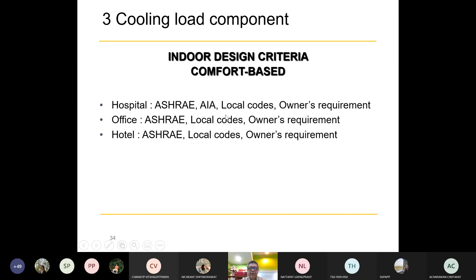The indoor design criteria depends on the comfort basis - maybe ASHRAE, AIA, local codes, or owner requirements. This is the basic one we normally use: temperature and air movement - in summer we use 24 to 26 degrees Celsius, in winter 21 to 23 degrees Celsius. Air velocity in summer is less than 0.25 meters per second, in winter less than 0.15 meters per second. Relative humidity in summer is about 40 to 50%, tolerable up to 65%; in winter around 25 to 30%. You can also see the ASHRAE comfort zone I showed in previous slides.